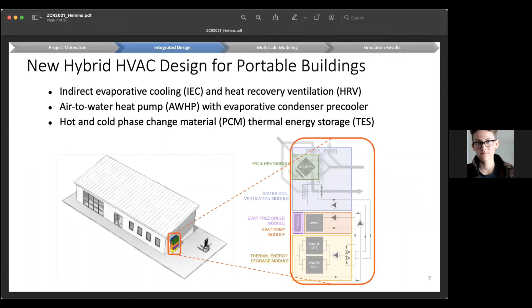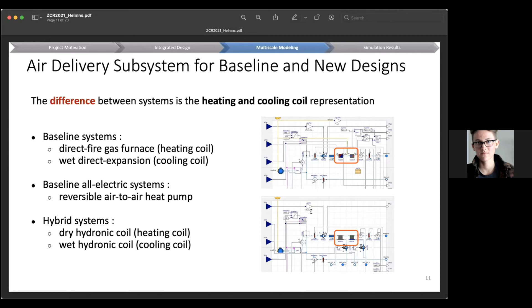Okay, thinking back about this modeling and these different subsystems, I'm going to touch briefly on the air delivery subsystem. We're modeling the baseline with gas heating and direct expansion cooling, baseline all-electric with an air-to-air heat pump, and our new system, the hybrid HVAC. We're able to capture the differences between these baseline systems and our new systems in the way we represent the heating and cooling coils. I'll show this diagram, though there's no expectation to really read anything in it. The main point is that we can reuse and reconfigure these object-oriented models, which cuts down time on our ability to run simulations and make predictions. We're really creating a tool that we're hoping people beyond the lab will be able to use one day.